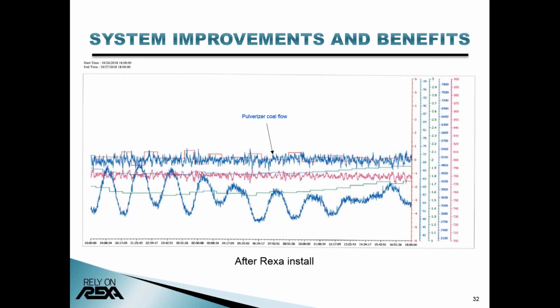Where previously we were cycling up and down with airflow in the boiler, we had to compensate by running excess air to control CO spikes, and we had to run excess ammonia to control the NOx spikes in the unit. Now we were able to bring excess air out of the unit, greatly improving our efficiency inside the boiler, and allowed us to run closer to our permit limits without having any exceedances.